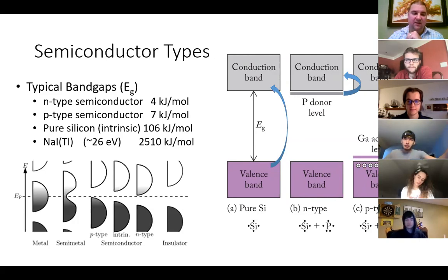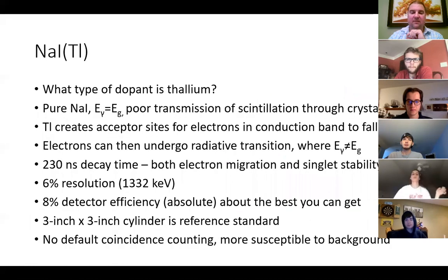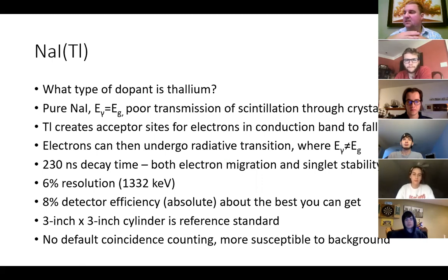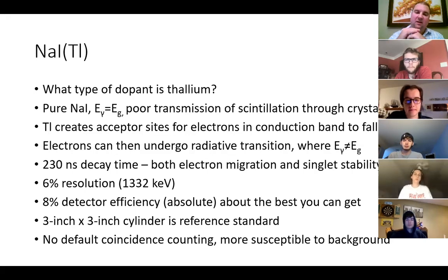For a solid scintillator like sodium iodide doped with thallium, thallium is electron poor — a P-type dopant into the sodium iodide. These create holes which electrons can migrate into. When they fall back down to the valence band, the emitted light energy is not as likely to be reabsorbed by the crystal itself. That is how near-instantaneous radiation energy deposition produces scintillation light emission.